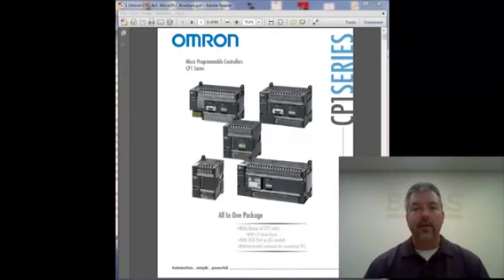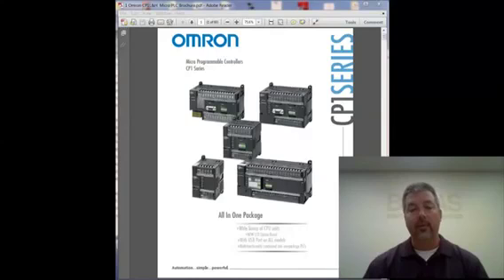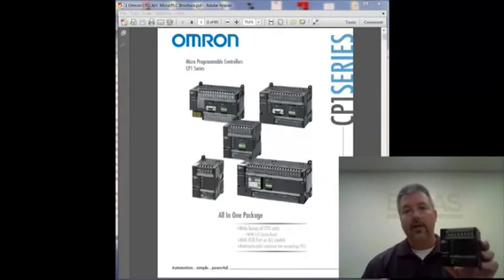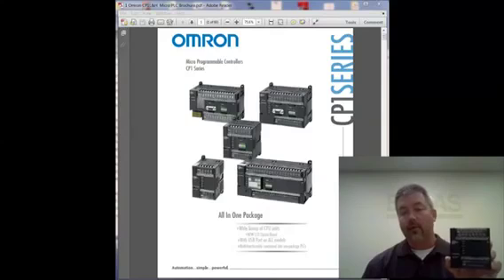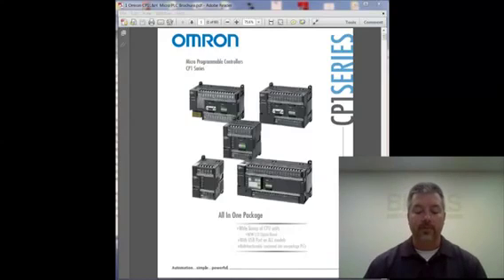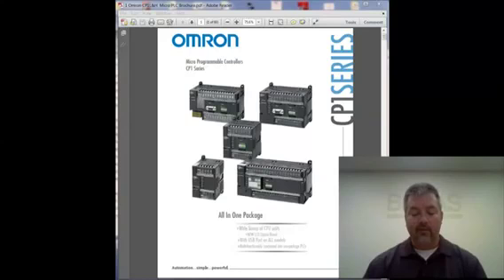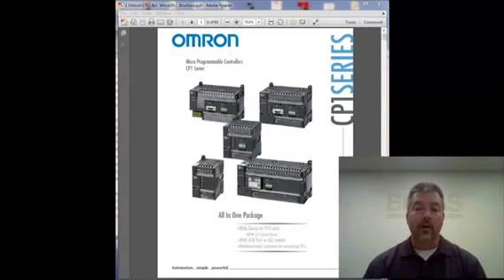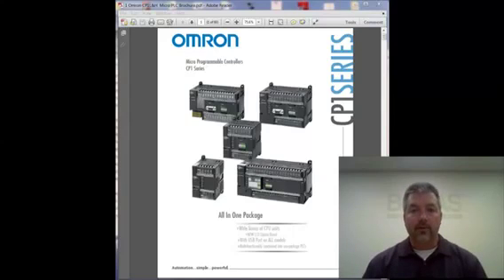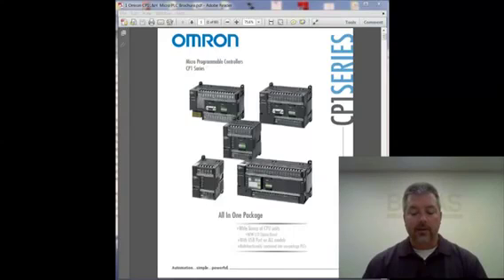Today I'd like to talk with you about micro PLCs and some of the motion capabilities that exist today. Many people aren't aware that even on a 10, 14, or 20 point PLC, you can do motion control. So on board we have four axes of pulse and direction or clockwise, counterclockwise pulse control that can be used for stepper or servo motion. It's rated at 100 kilohertz and it's very effective for motion applications.